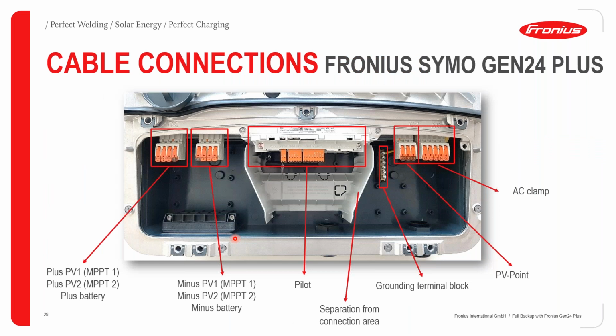Just to keep you abreast with the cable connections, a brief summary, as you can see. We have the DC point where you connect your PV cables, and then of course your battery cables. You have the Pilot, which is integrated with the communication modules for connection to the smart meter and the battery box, as we will see subsequently. And then of course the AC connection point. Of course we have the PV point, but this will be a topic of discussion in a subsequent webinar. But today we are discussing full backup of the Primo Gen24 Plus inverter.